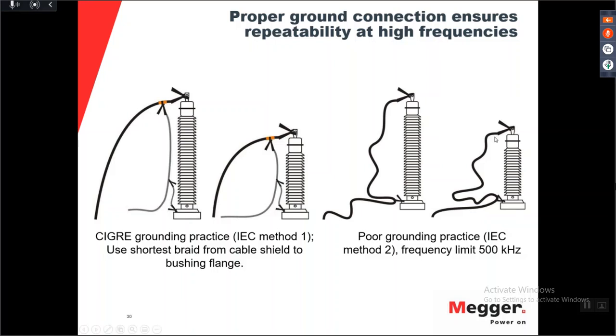Here you can see a typical example of something that is not recommended, the second method, which gives you a frequency limitation of the highest frequency. Because if you have a cable that is connected properly at the top, and then you have an accessible point for the ground point here, and then you connect it correctly at the bottom of the flange of the bushing, you can see how this cable creates a worm.